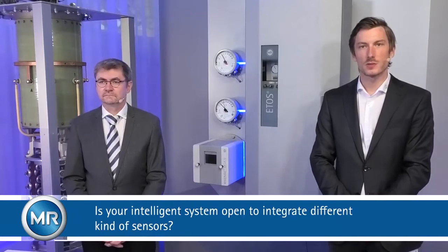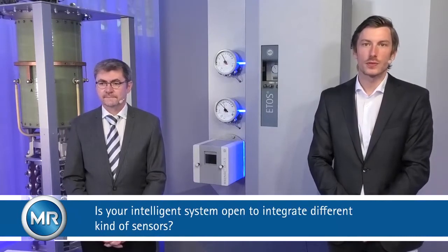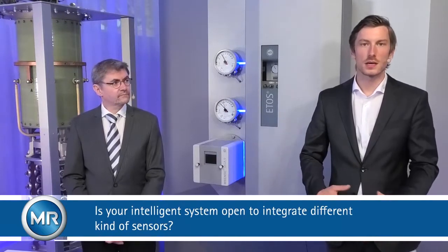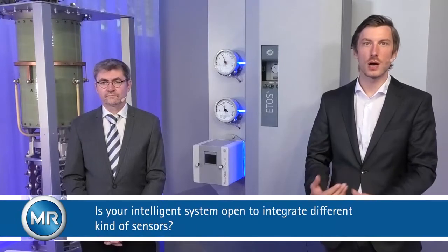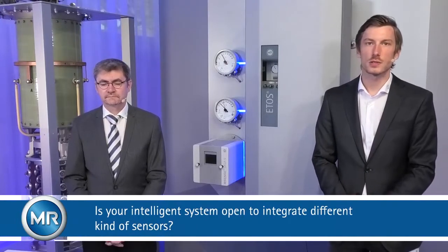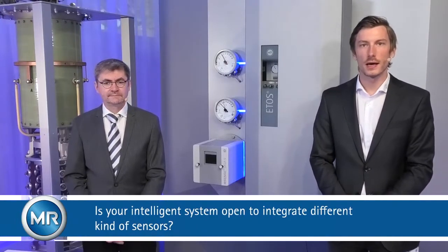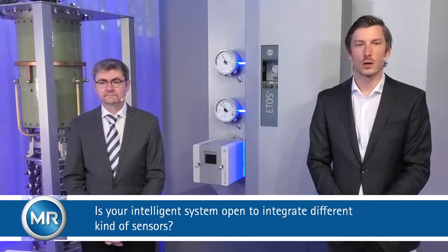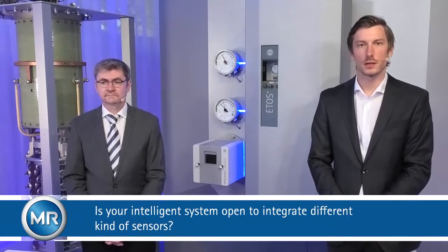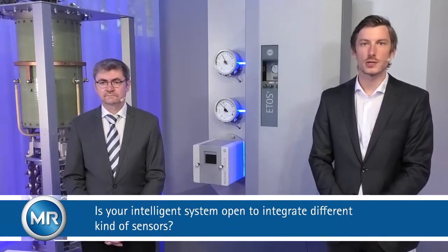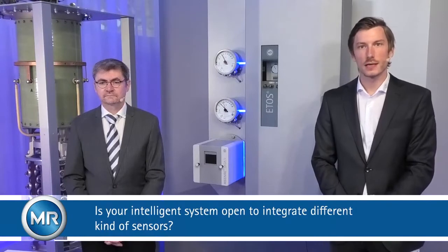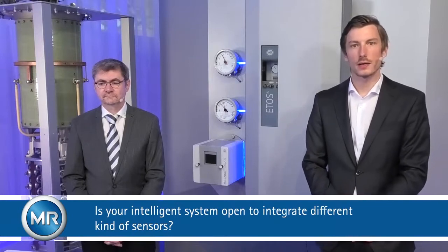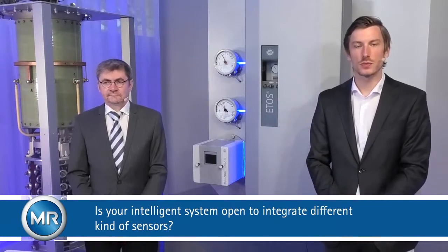And it's possible, if these sensors also have a standardized way to communicate, and it is described in the operating system, to integrate it into ETOS. We have pre-installed the more typical sensors, like a temperature sensor, oil level indication, and all these kinds of sensors already. So once it's all wired, you just map the functions to the signals.